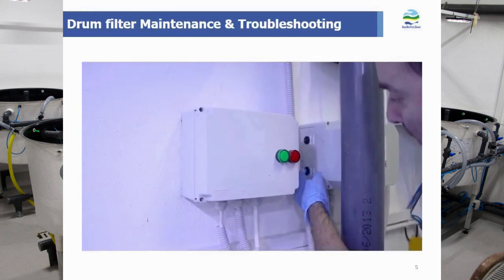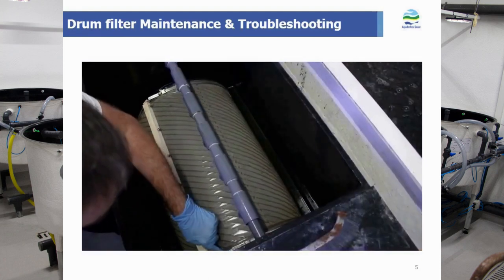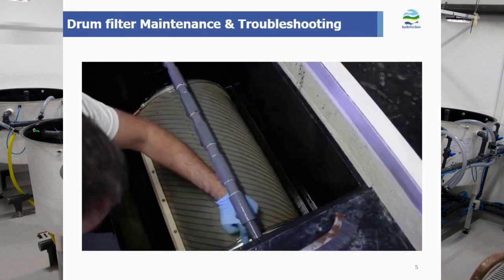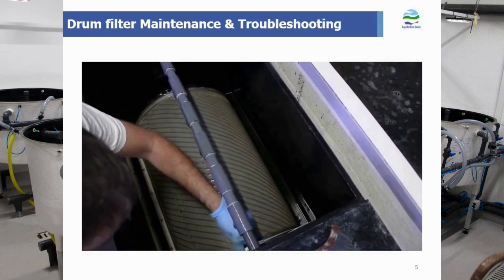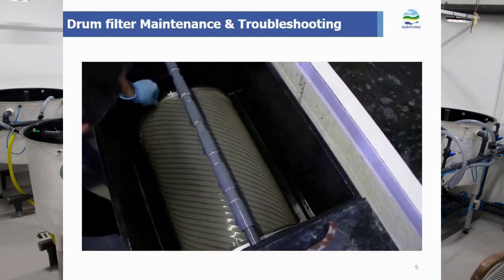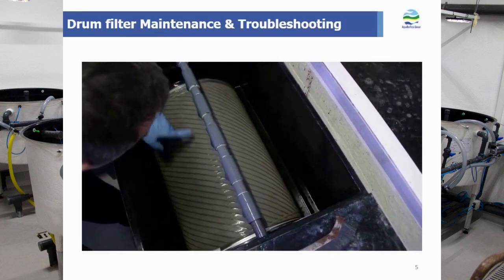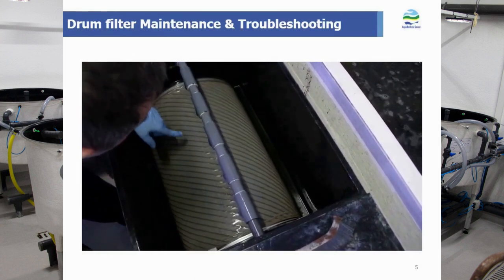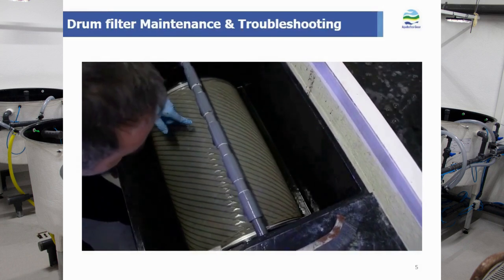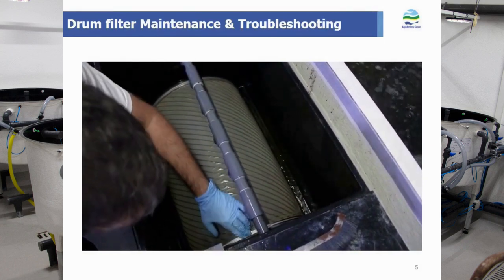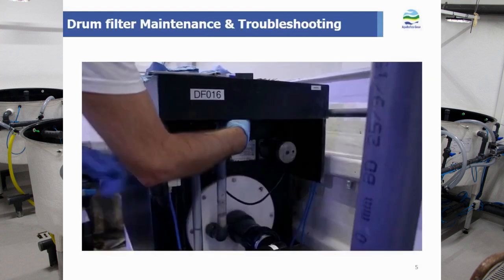To check the mesh, turn off the pump but remember to leave the drum filter button on. Then ensure the mesh is well placed under the jubilee clips at both edges of the drum and inspect all the surface to ensure there are no holes. The mesh should be replaced in case of damage that could compromise its operation. If the hole is relatively small, it is possible to fill it with food-grade silicone glue. In case of larger damage, the mesh needs to be replaced.